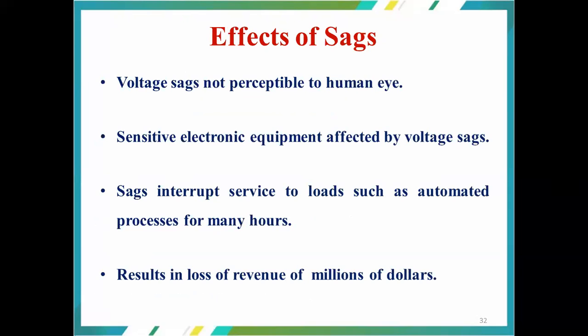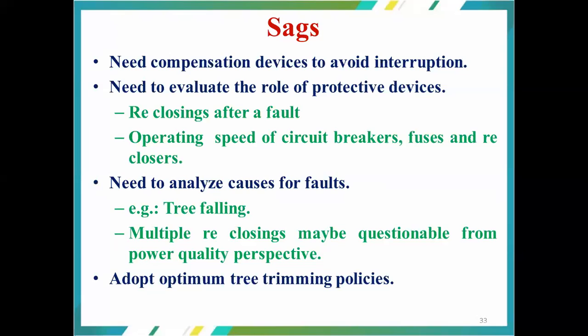And sensitive electronic equipment is affected by voltage sags. Under-voltage operation may result in underperformance or a reduction in efficiency, etc. Sags interrupt service to loads such as automated processes for many hours. And automation is another area, like the EV. Almost all industries are opting for automation, so any voltage sags may adversely affect these automated plants. Because of this, it results in a loss of revenue of millions and millions of dollars or rupees. And sags need a compensation device to avoid interruption.